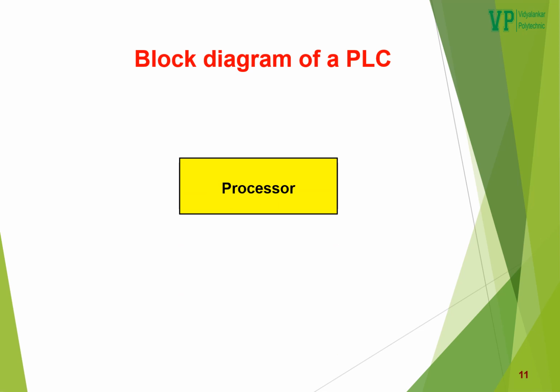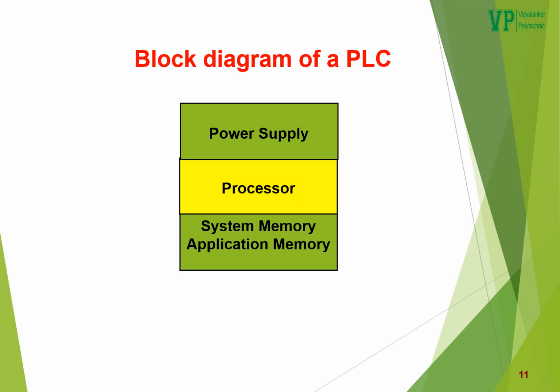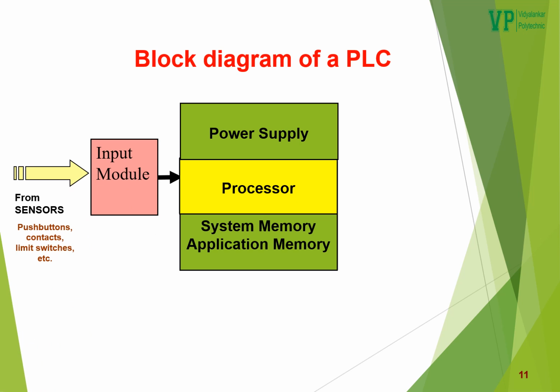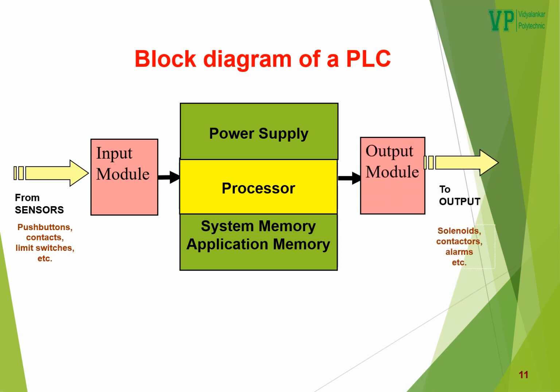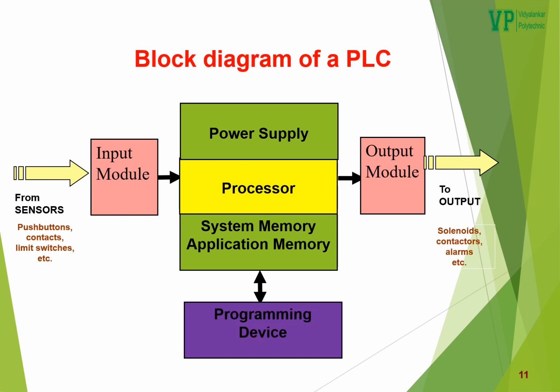Let's start with the block diagram of a PLC. To begin with, a processor, power supply, memory, which has two sections, system memory and application memory, and the input module. This input module is connected to the processor with an optical isolation, and the field devices are connected to the input module. This optical isolation keeps the processor safe from the field devices. Just as there's an optical isolation at the input side, so does the PLC have an optical isolation at the output side. That is, there's an optical isolation between the output module and the processor, and the output devices are connected to the output module. Then there's a programming device. Well, the programming device is one device which is used to feed the ladder diagram to the PLC.